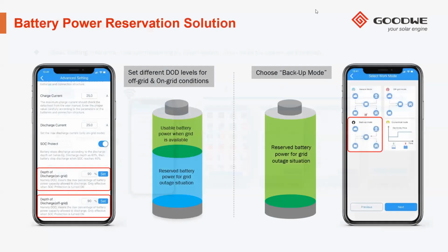So we have battery power reservation under our advanced settings, which we will go through in more detail. There's an on-grid and off-grid depth of discharge. When you are in the self-defined general mode of our inverter and you are using self-consumption, you can use a portion of your battery for self-consumption and reserve the rest for grid outages. If your battery capacity is insufficient to keep you through a long outage, or if your PV production is less than your consumption, then you can set it to backup only, which reserves all the battery power for grid outages.